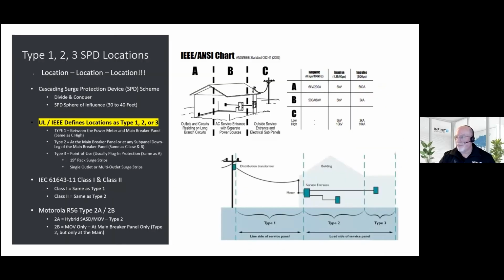So where to install them? Well, IEEE and UL came up with, this is an older chart, but it refers to these A, B, C locations. This is a newer one, where they've gone to Type 1, Type 2, and Type 3 location certified surge protectors. So this is kind of backwards, but C is similar to Type 1, which means the surge arrestor will be installed between the meter and the main panel. Not at the main panel, but between those areas. So that surge arrestor, to be Type 1 rated, has to be built a little stronger. It has to be able to handle more current than a surge arrestor that's not Type 1 certified.